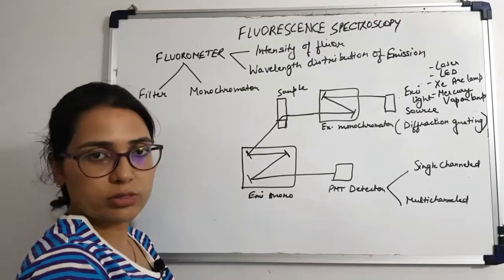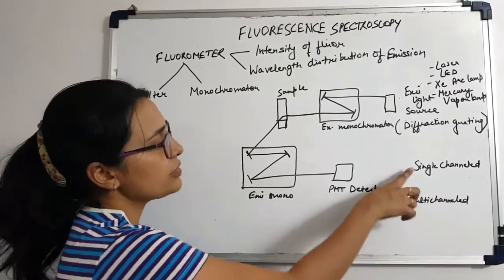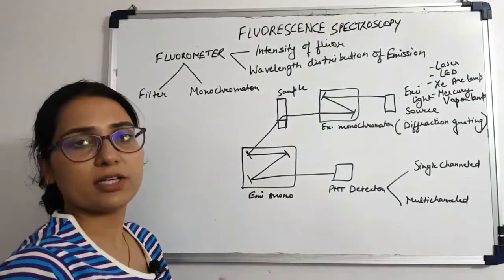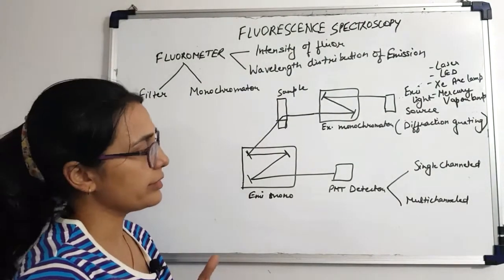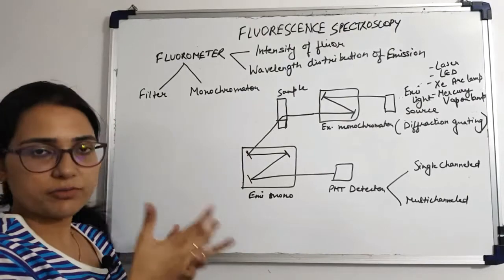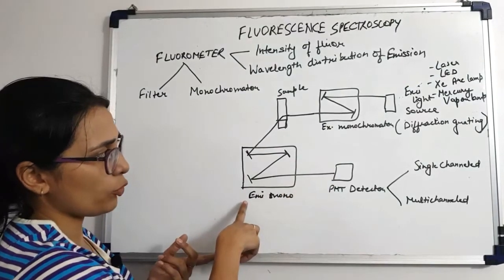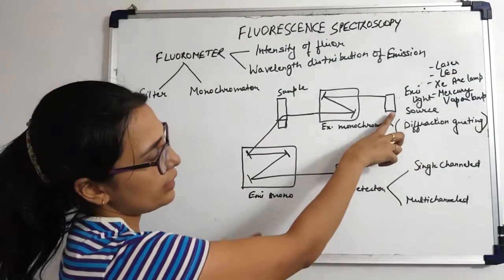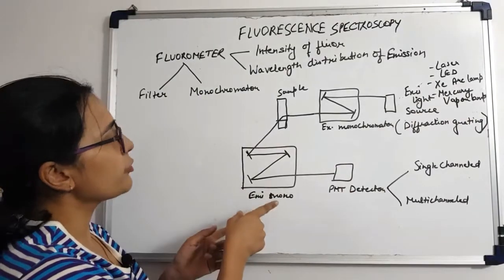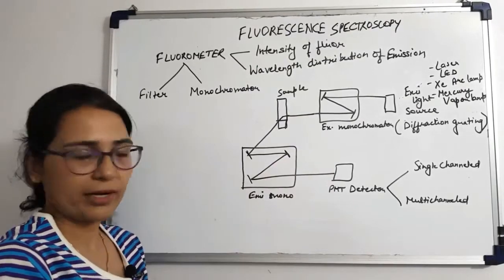The detector used in fluorescence spectroscopy can be either single-channeled or multi-channeled. A single-channel detector can only measure the intensity of one wavelength at a time, while a multi-channel detector can measure the intensity of all wavelengths simultaneously — so if you're using a multi-channel detector you don't need an emission monochromator. The most versatile fluorometers used today consist of two monochromators — one excitation and one emission — and contain a xenon arc lamp as the excitation source, allowing generation of both excitation spectra and fluorescent spectra.